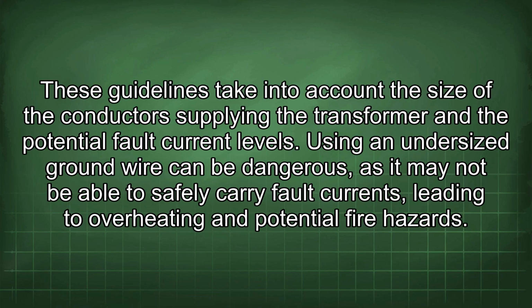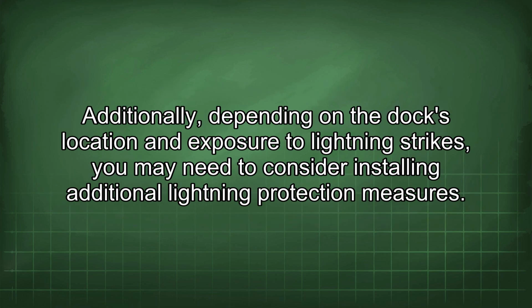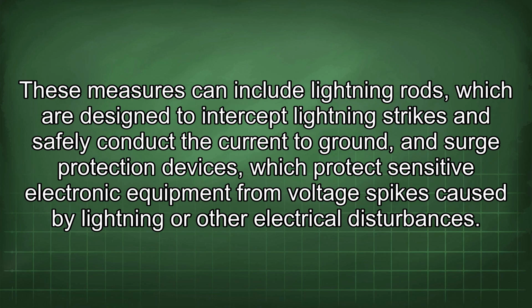The ground wire must be sized according to the NEC guidelines. These guidelines take into account the size of the conductors supplying the transformer and the potential fault current levels. Using an undersized ground wire can be dangerous, as it may not be able to safely carry fault currents, leading to overheating and potential fire hazards. Additionally, depending on the dock's location and exposure to lightning strikes, you may need to consider installing additional lightning protection measures. These measures can include lightning rods, which are designed to intercept lightning strikes and safely conduct the current to ground, and surge protection devices, which protect sensitive electronic equipment from voltage spikes caused by lightning or other electrical disturbances.